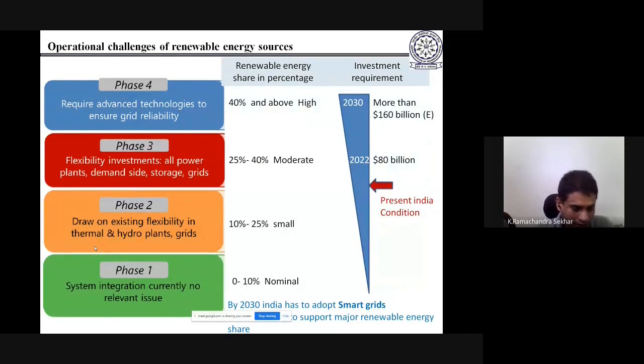Ideally, this source should exhibit its own current characteristics, immediately trying to give its own current demanded by the fault. But at that time, the source itself may cause oscillations, as it may not be sufficient to give that much current instantaneously. So the voltage will fall at the point of common coupling, PCC.